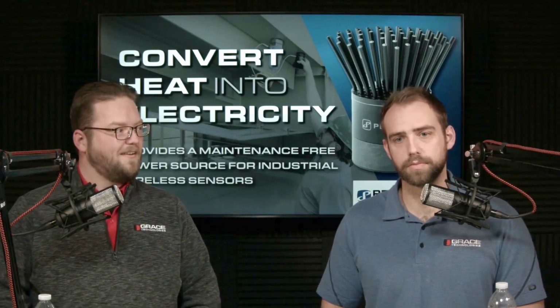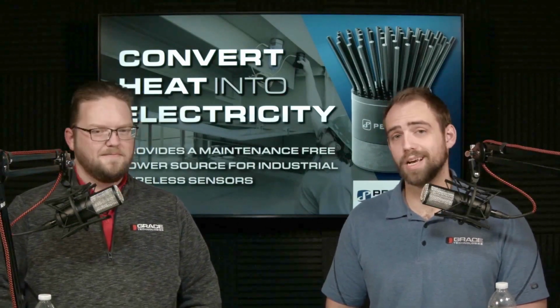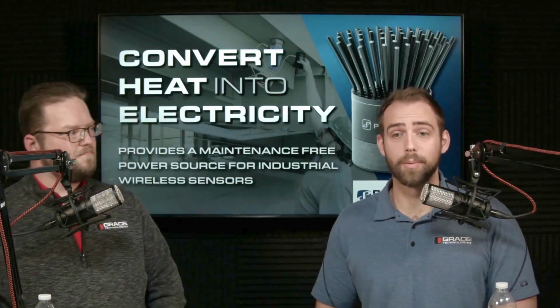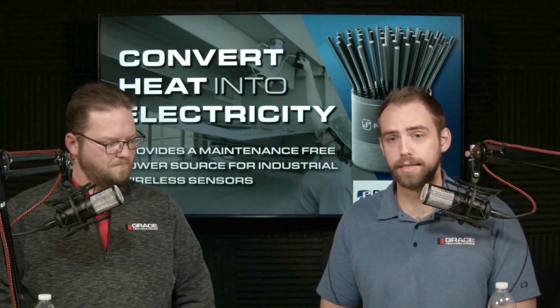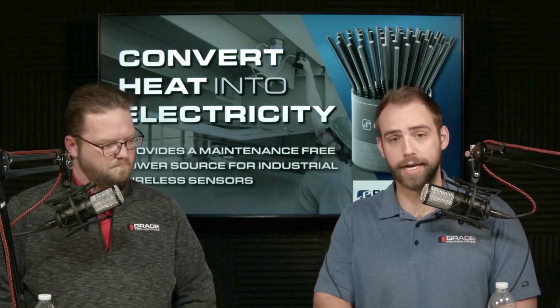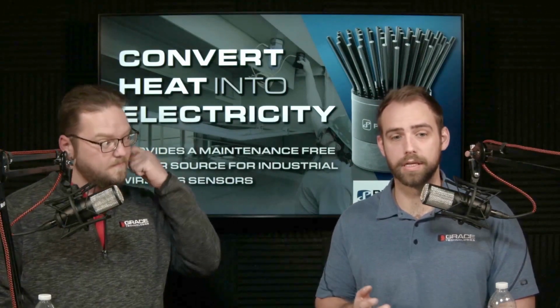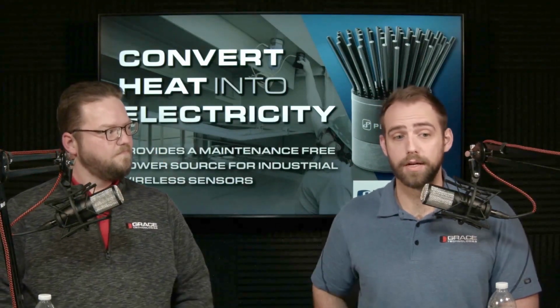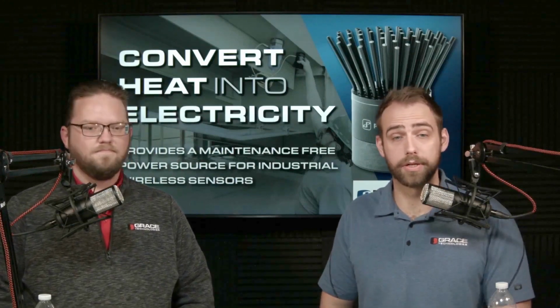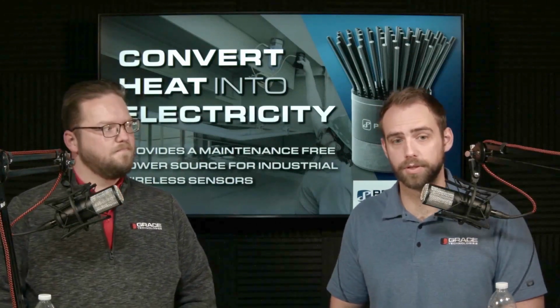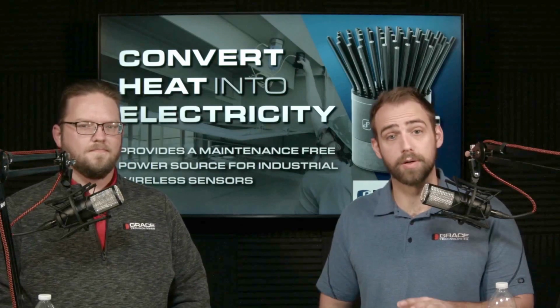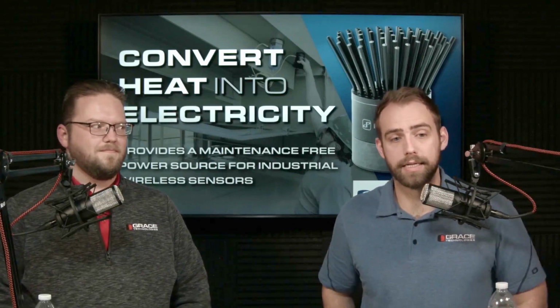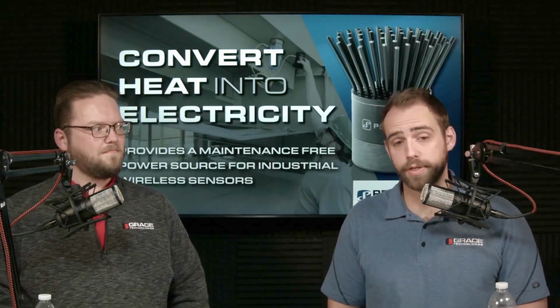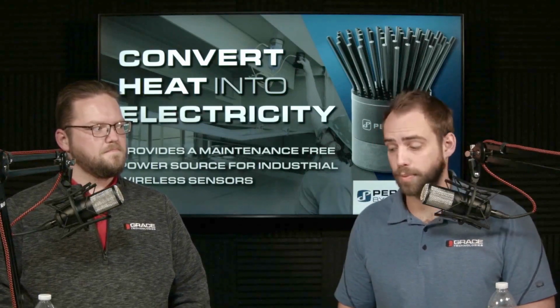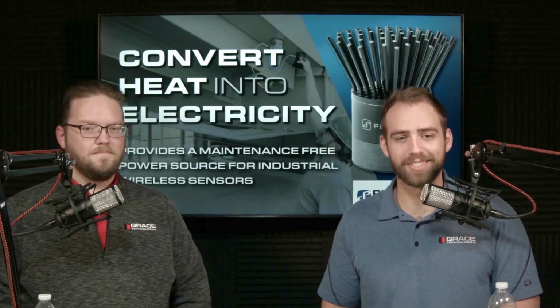It definitely caught attention. One of the most common questions we get is how much of a temperature differential you need. Typically if you can place your hand on a motor or pump and it's just warm to the touch, that's plenty. But in raw numbers, it's about 30 degrees Celsius differential needed from the surface of the motor or pump to the ambient air. These are very frequently installed in oil and gas applications, where hitting that differential is basically no problem.